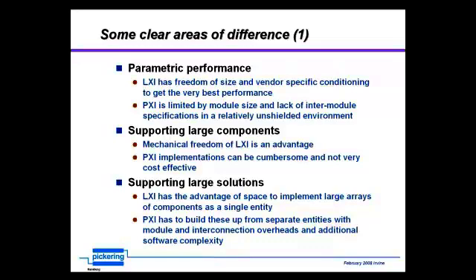LXI has this freedom of size and vendor-specific conditioning, so we can have different power supplies and different cooling within an LXI-defined product. But PXI has limitations on module size, and there is a lack of inter-module specifications, which can be a problem — shielding is relatively undefined. Supporting large components is something switching systems often have to do, and the mechanical freedom of LXI is really quite a significant advantage.